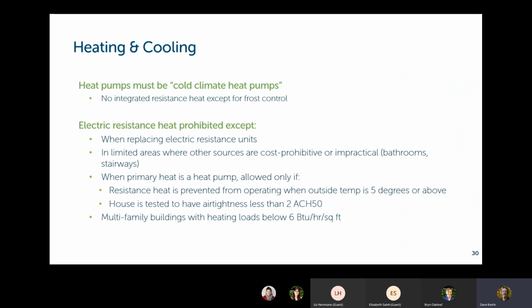And electric resistance heat is also allowed in multifamily buildings with heating loads below 6 BTU per hour per square foot. So in other words, very, very efficient buildings that don't need much heat. And in that case, only multifamily. And this is just a side note that electric resistance heat is not allowed in Burlington without the approval of the Burlington Electric Department. This is not in the Vermont code, but as long as we're talking about electric resistance heat in Vermont, probably worth noting.